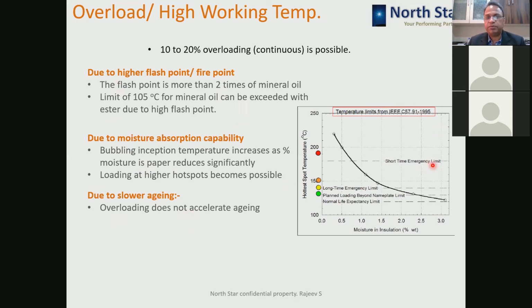So due to higher flash point, the flash point is more than 2 times that of mineral oil, and the limit of 105 degrees centigrade for mineral oil can be exceeded with ester due to high flash point. So you don't have to worry that it is going to catch fire when I increase the load. So you can safely increase the load, and you can take the load even up to 120 or 125 degrees centigrade. So that much overloading you can do without any problem.